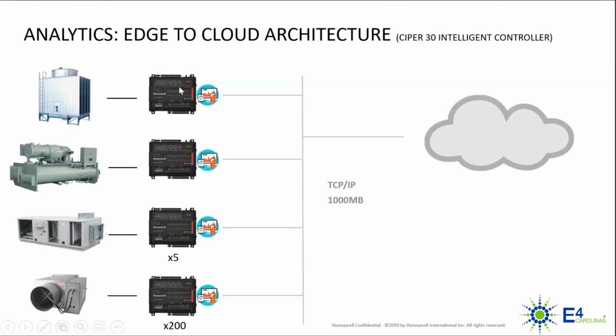What I'm showing here is one of these IP-enabled high-speed field controllers. This one's controlling a cooling tower; others control a chiller, air handler, VAV box, etc. Baked right into the control sequence, we have fault diagnostic edge analytics, continuously checking in with that equipment, asking if it's running okay, and alerting us if something's wrong.